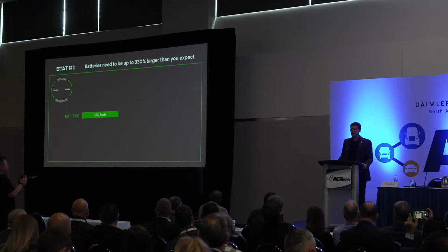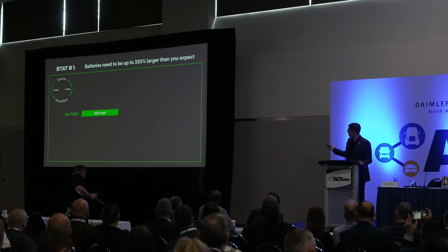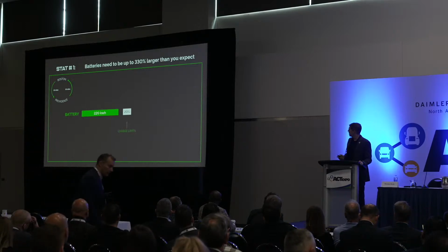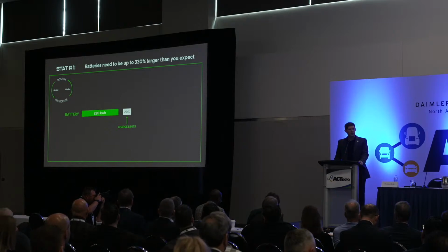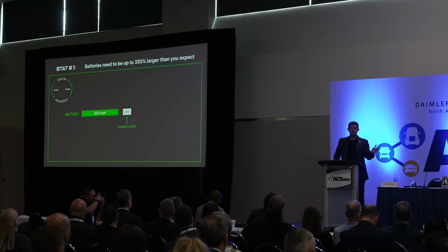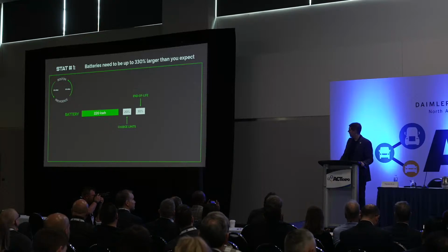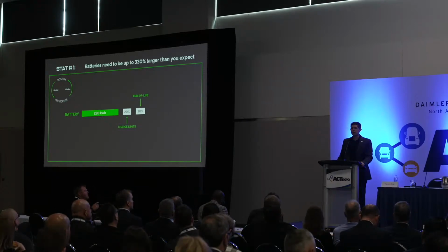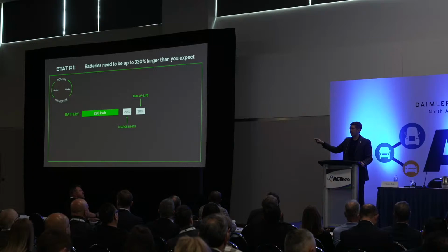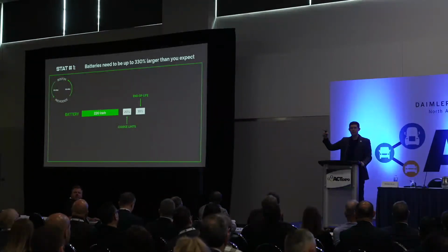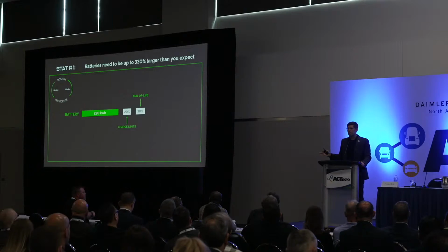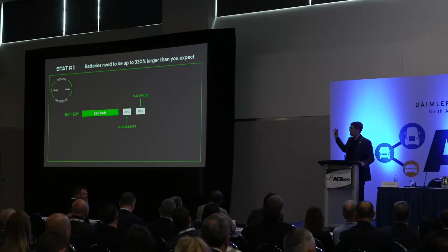But let's break down some limitations batteries face. You start with 220 kilowatt hours, but there are charge limits on battery packs. You don't want to charge above 90%, and you don't want to charge below 10%. So that increases your pack size by 20%. Similarly, if you run that same round trip every day for 5 years, you need to size your battery pack based on the end-of-life capacity, not the starting capacity. Over the life of a battery pack, capacity is expected to decrease by about 30%, so that adds another 30% capacity needed.